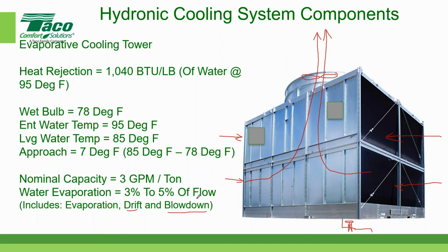So you have to add enough water to compensate for the blowdown, the drift, and the evaporation. And generally speaking, that's 3 to 5% of the condenser water flow. So in our case, if you had a cooling tower and you had 3 GPM per ton, that's 3,000 GPM. If I multiply that by 0.03, that's 3%. I would need 90 gallons per minute of makeup water to the tower in order to compensate for evaporation, drift, and blowdown. Cool stuff, isn't it?